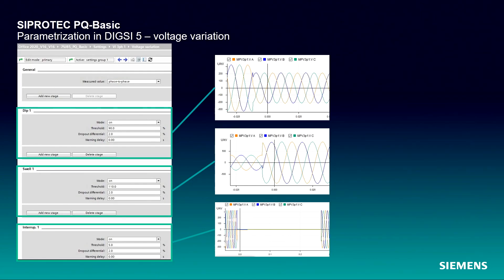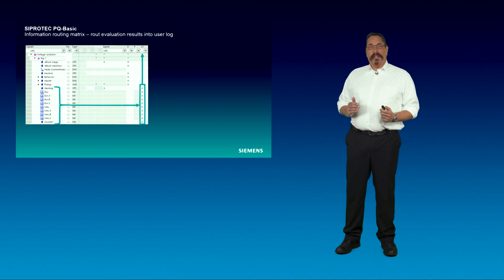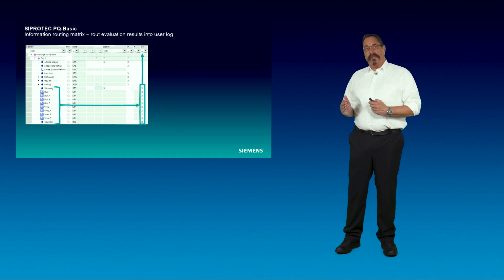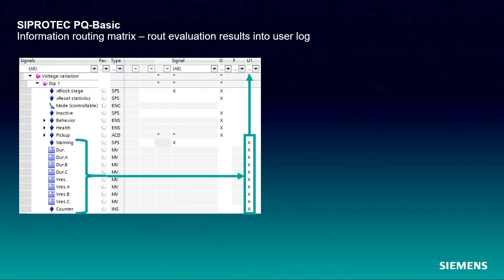Voltage variation: let us now take a look at the parameterization for voltage variations. The default configuration of thresholds and dropout differentials is already conformed to event classification standards. The information routing matrix: let us do information routing for voltage variations. The event indication and relevant evaluation results, like phase-related duration and extreme value, can be easily routed into logs using the information routing matrix.